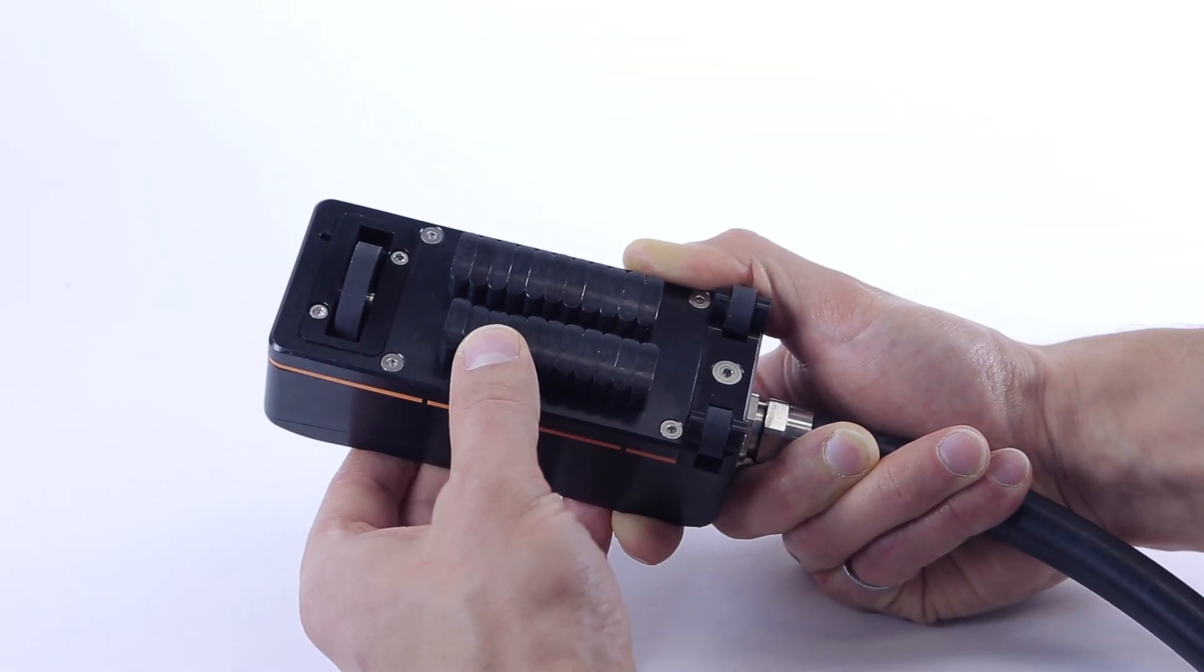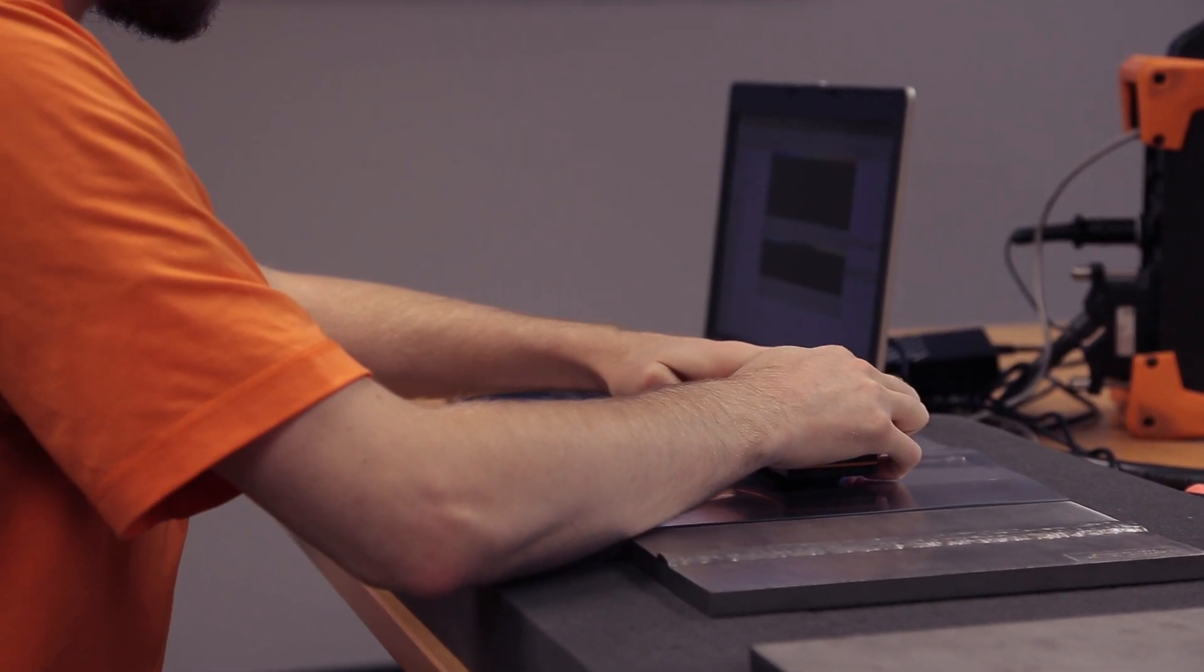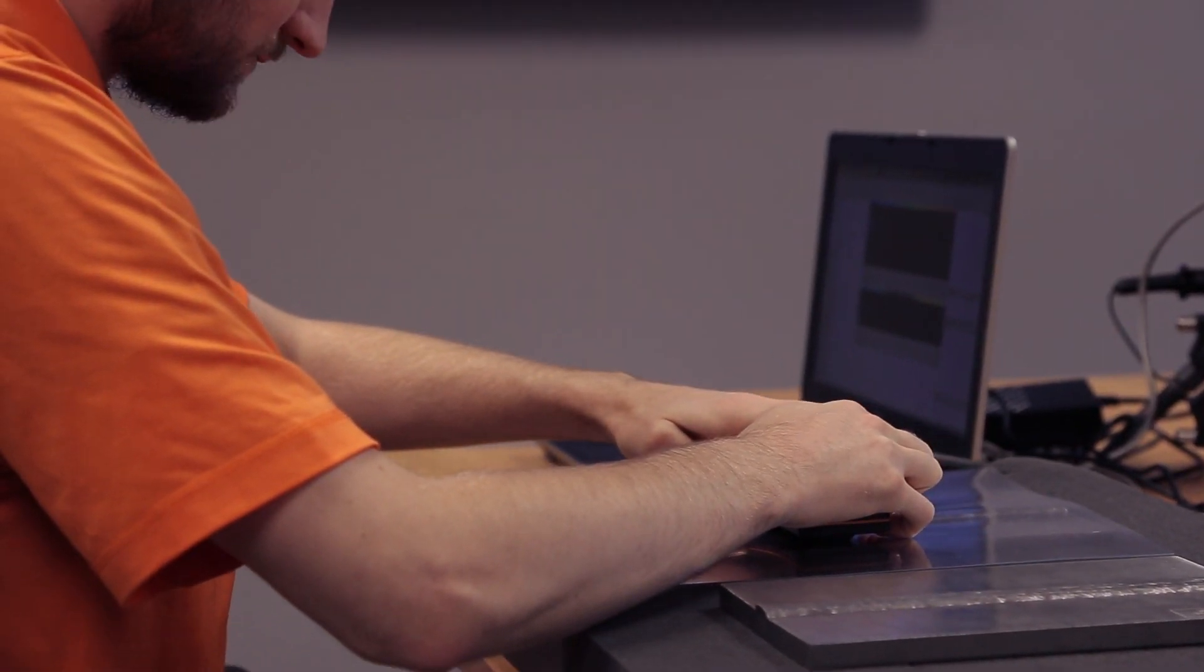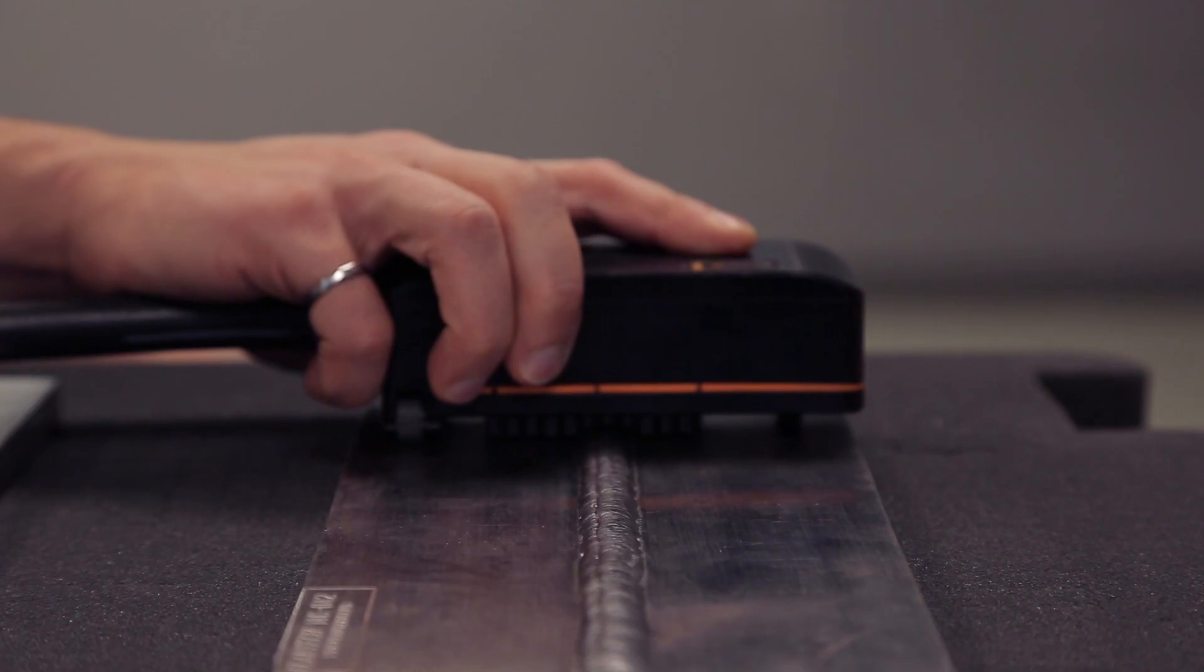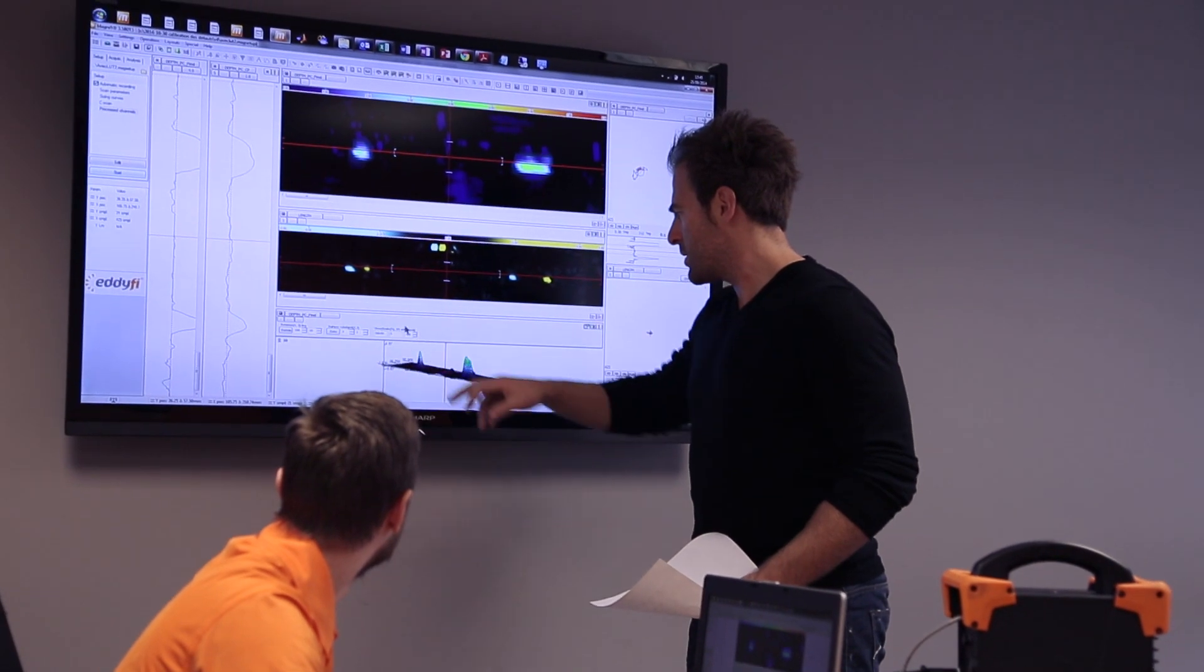The Shark was designed so that its spring-loaded fingers adapt to butt-weld crowns. These fingers enable the probe to scan the weld cap, the toe area, and the heat-affected zone in a single pass with uniform sensitivity.